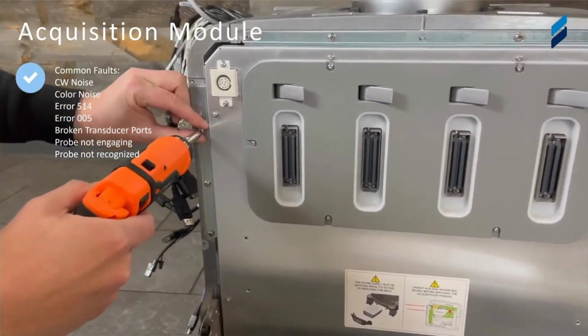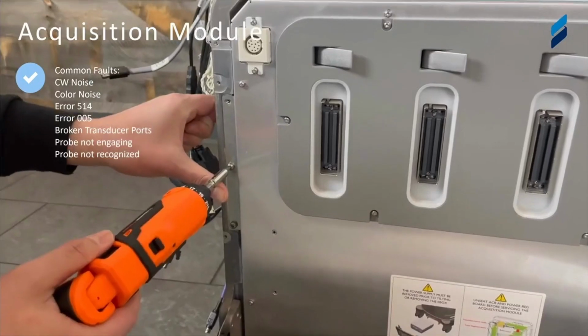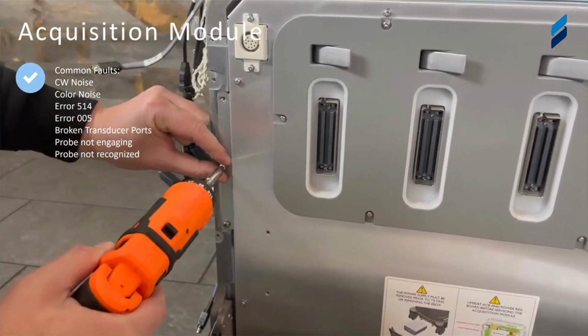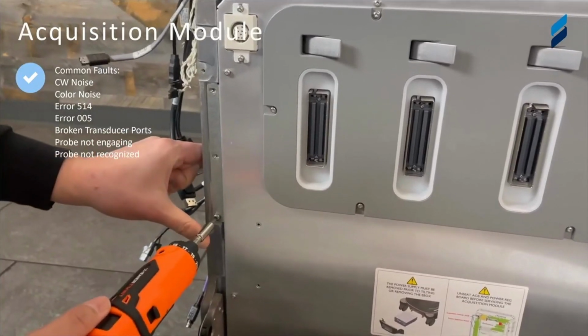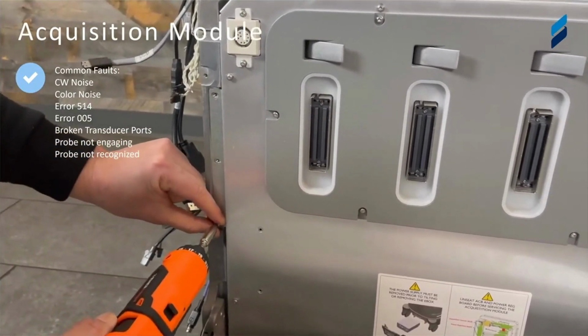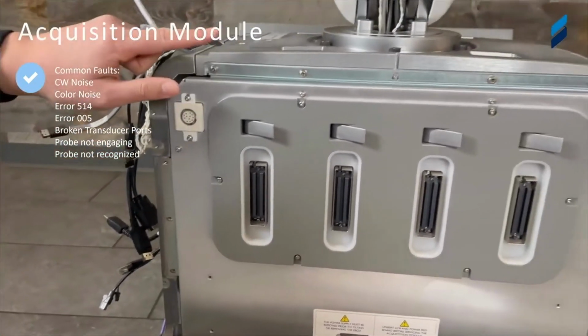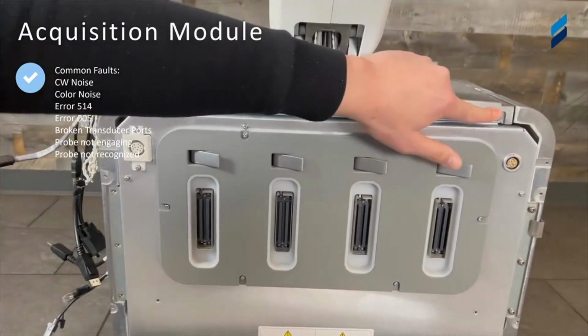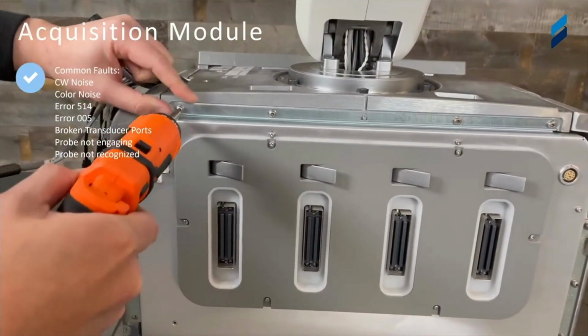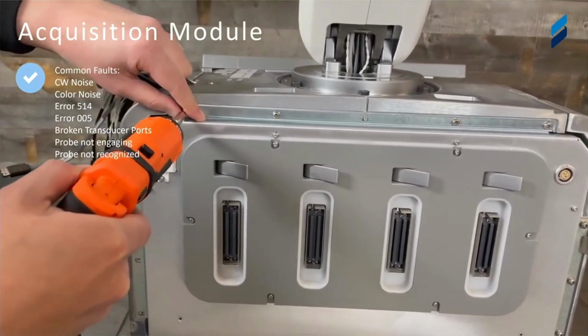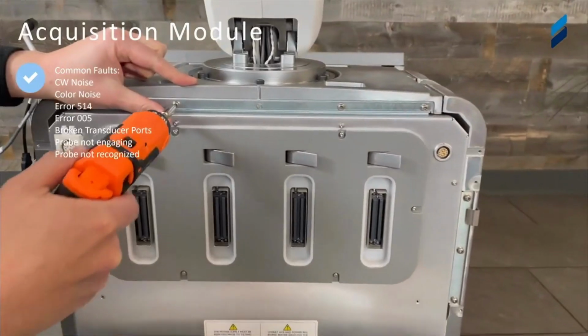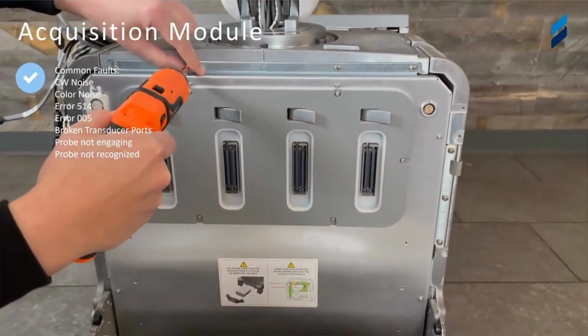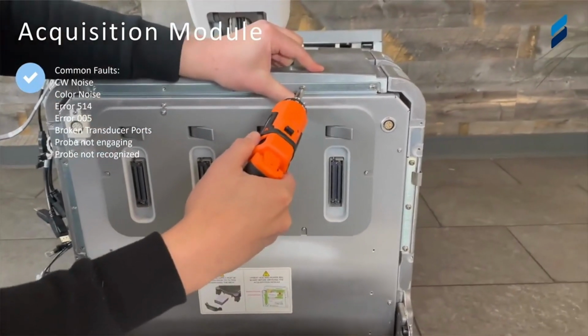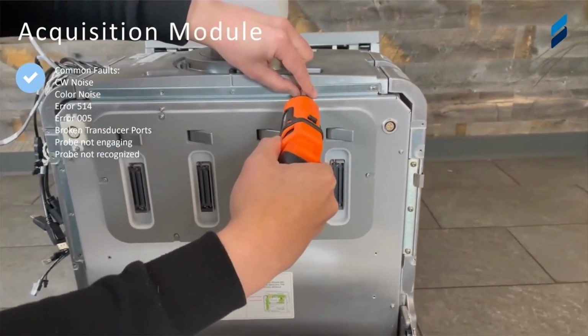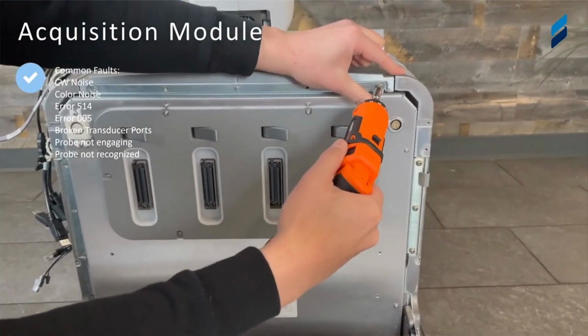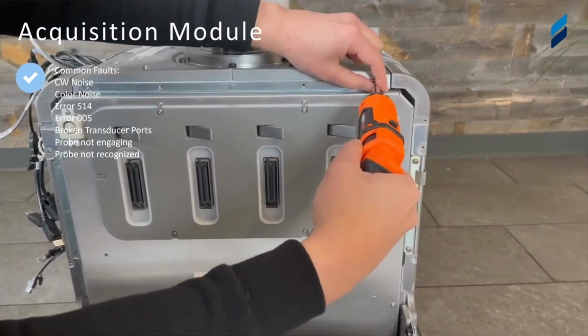So now that we have the cables out of the way, we're going to remove all the screws around the perimeter of this metal chassis. And what's going to happen is that we're going to tilt this assembly forward. That's going to be your Ebox and your acquisition module. You're going to see this process a few times in this training. We're moving at real-time speed here, and we just wanted you to see it a few times so you're comfortable with the process.